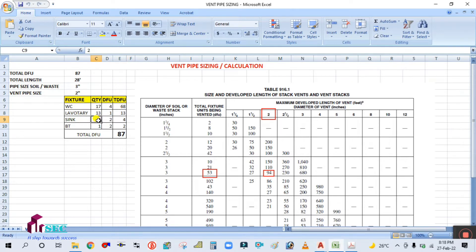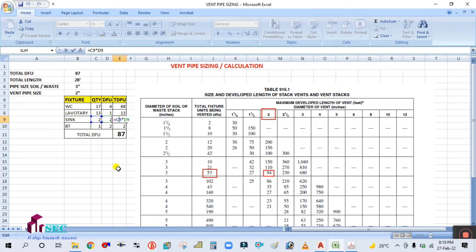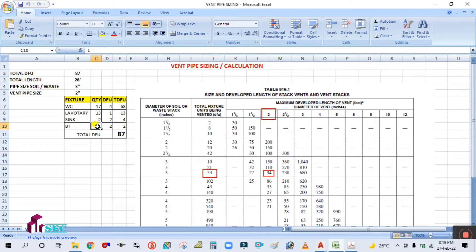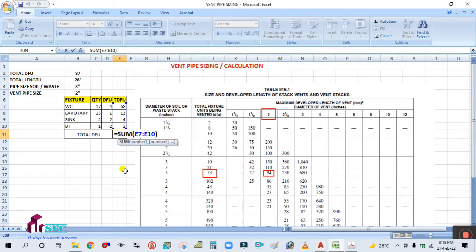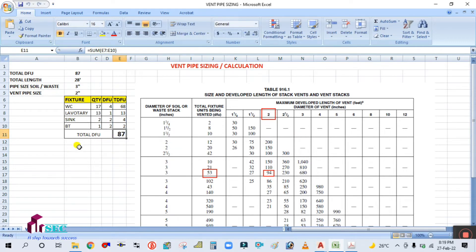Sink — the drainage fixture unit for the sink is 2, and the quantity is 2, so multiply: 2 into 2 equals 4. Bathtub — the drainage fixture unit for the bathtub is 2, and the quantity is 1, so you get 2. The sum of the total drainage fixture unit is 87.